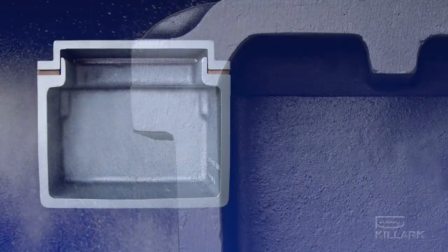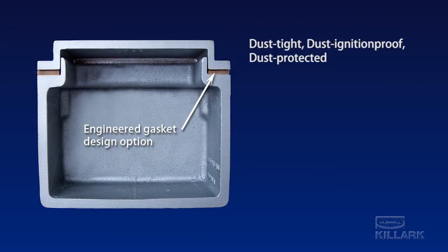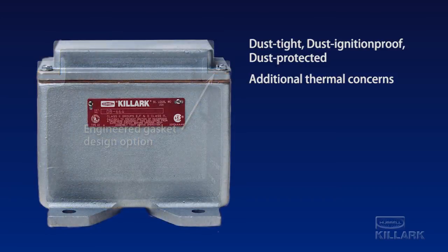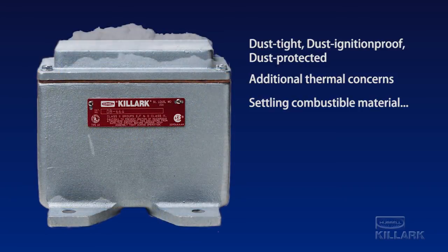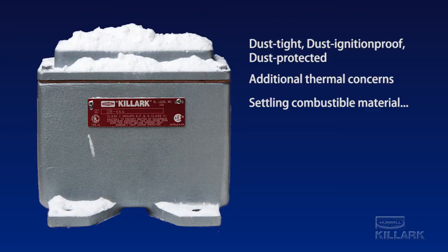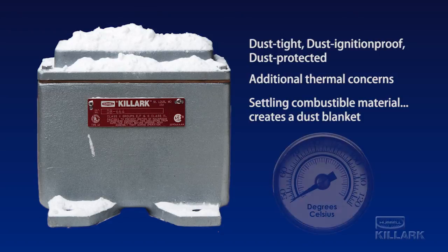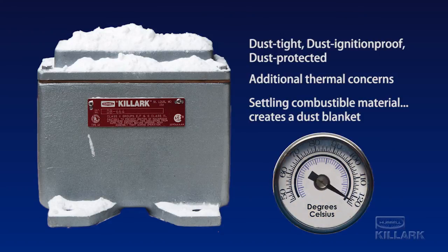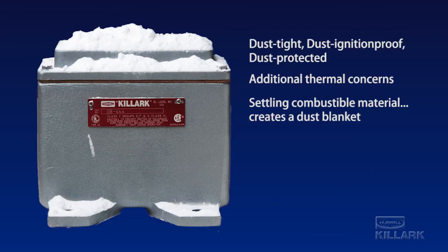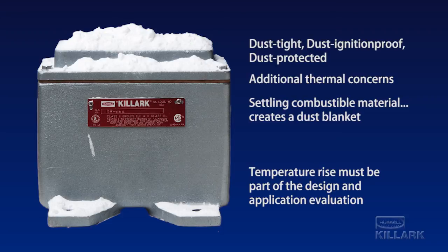This increased dependence on dust-tight, dust-ignition-proof, and dust-protected housings to address the risk of explosive dust clouds, however, introduces additional thermal concerns. Despite maintenance and housekeeping programs that may be in place at dust-producing facilities, the assumption must be made that the combustible material could settle on electrical enclosures and apparatus. The resulting dust blanket could cause the internal devices to operate at elevated temperatures, even under normal operating conditions. Additional engineering considerations are required to deal with the impact of the dust blanket by both the equipment manufacturer and the user.